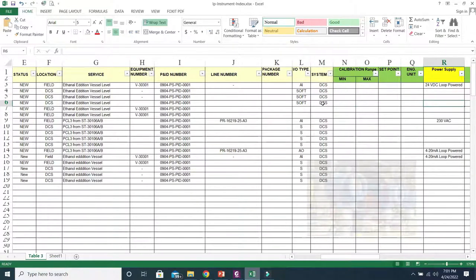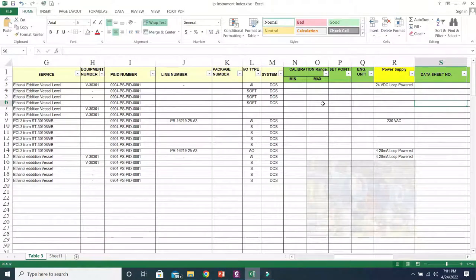Then calibration range. For each instrument there will be a calibration range, and if it is a switch or if it is working on a different set point, then we need to provide the set point as well. So calibration range and set point will be required in the instrument index also. Although in the beginning of the project we will not have this information, after the preparation of material requisition of field instrumentation, we will have the calibration range and set point, so we can update later on. Okay, and engineering unit as well. Although we know the engineering unit, we can update it otherwise during the updation of calibration range or set point.